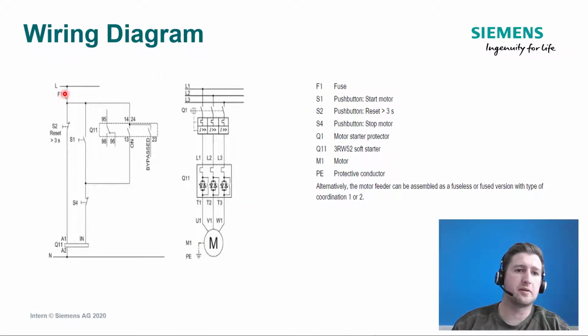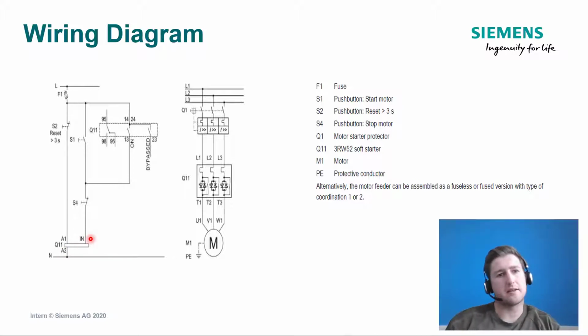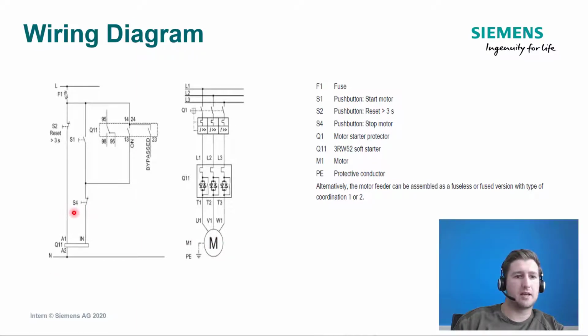To wire the device in the control circuit, as you can see here, you've got your A1 and your A2 terminals, and you've also got your in signal. And that's all you need to start the soft starter really. S1 is to start the motor, S4 is to turn the motor off. So if we were to initiate a start here, we press S1. The S4 circuit here, as you can see, is already continuous. So as soon as S1 is pressed, you already have your control voltage supplied, so the motor would initiate a start. If you were to break that circuit with S4, which is the stop command, that would immediately bring the motor to a standstill through a coast.